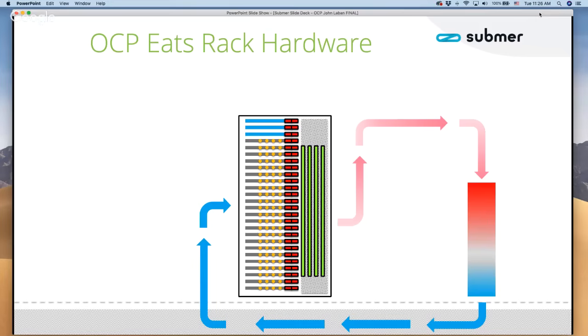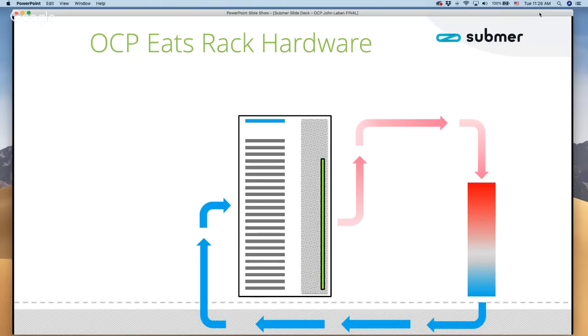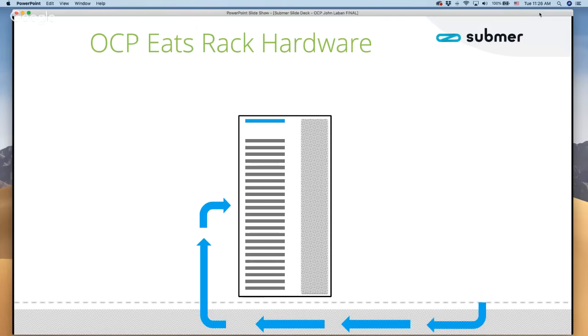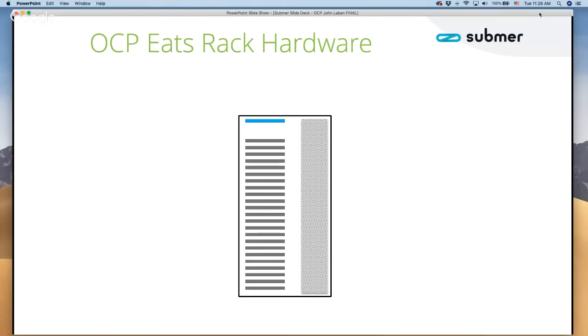Now we start to rip the gear out and throw it away. We throw away all those fans, hundreds of them. We throw away all the AC to DC power supplies, 2 in every server and every switch. We throw away some of the top of rack switches since we don't use them the same way anymore. We throw away all those $1,000 AC to DC power strips. We throw away the downflow CRAC unit because we don't do it that way anymore. We remove the floor since you don't need it. And we throw away all that cable spaghetti at the back of the rack.